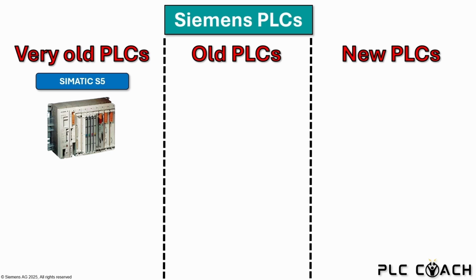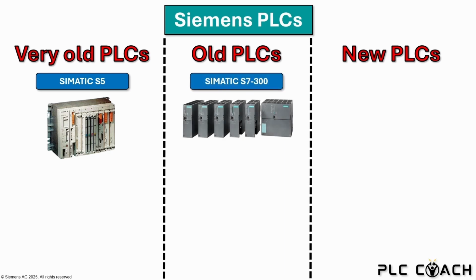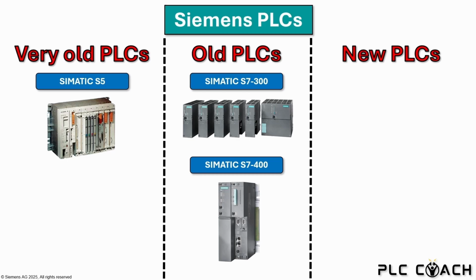In 1994, the new generation of controllers Simatic S7 was launched. This includes the devices Simatic S7 300 and Simatic S7 400. The S7 300 is used for small to medium-sized systems, while the S7 400 handles larger, complex applications. You can still order S7 300 and 400 controllers, but starting in 2025 they will only be available as a spare part. Even in 10 to 20 years you will find these PLCs widely used. However, new systems will usually no longer be equipped with this generation of controllers.